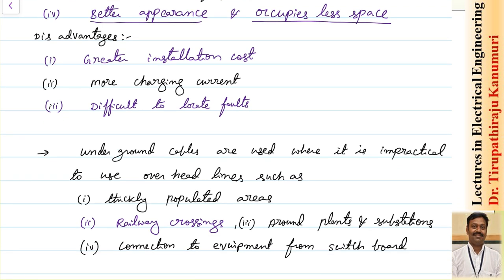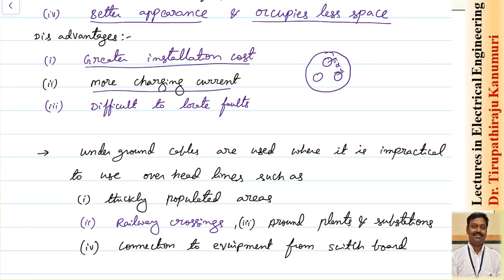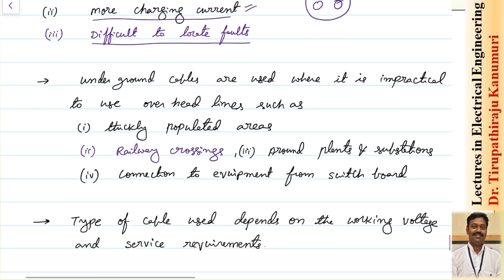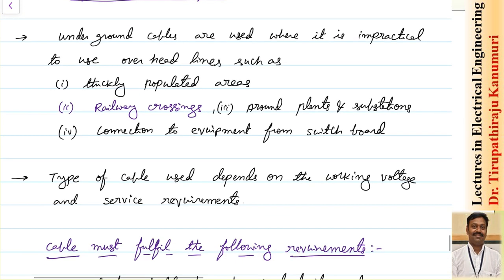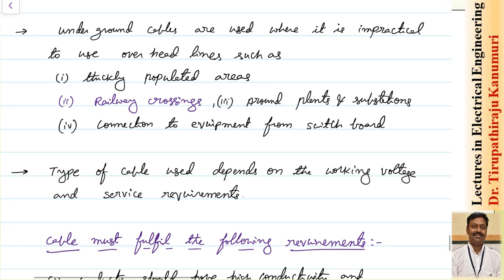The disadvantages of underground cables include greater installation cost. In cables, adjacent conductors are placed very close together, so capacitance is higher, leading to more charging current compared to overhead lines. It is also difficult to locate and diagnose faults in a cable. Joints or connections can only be made at junction boxes via manholes — it is impractical elsewhere. These limitations mean underground cables have high initial cost, difficult fault location, and more capacitive charging current.